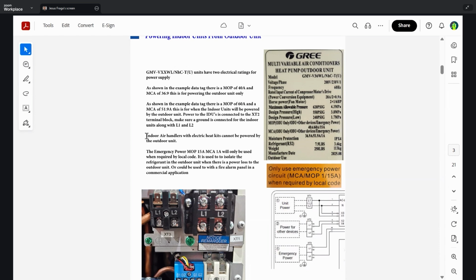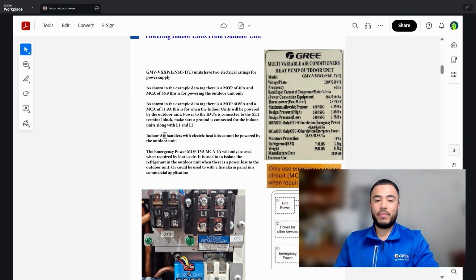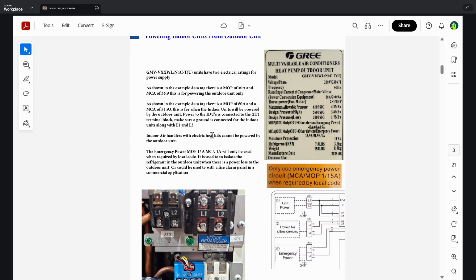So, as I had stated earlier, for the units that are utilizing heat kits, this will not be applicable to those units as the heat kits do pull more amperage. And the wire that is supplied from the outdoor unit to the indoor units, it will not be able to support that heat kit once it is engaged. So if any of the indoor units do have heat kits, please use a dedicated line of power from the panel. That way you don't run into any problems with inspectors.